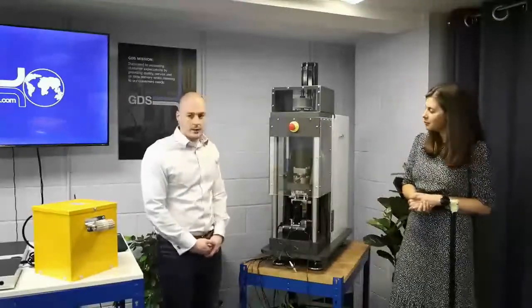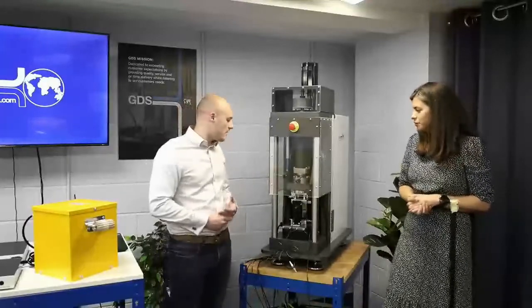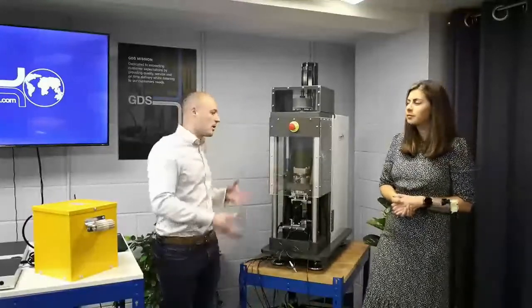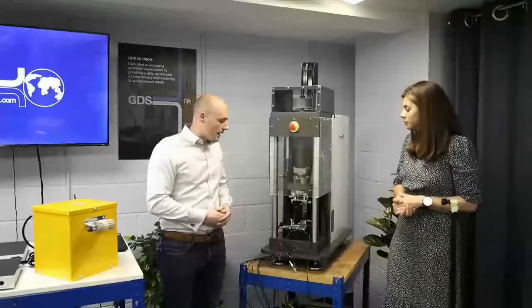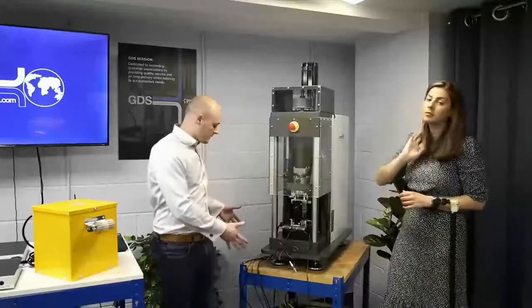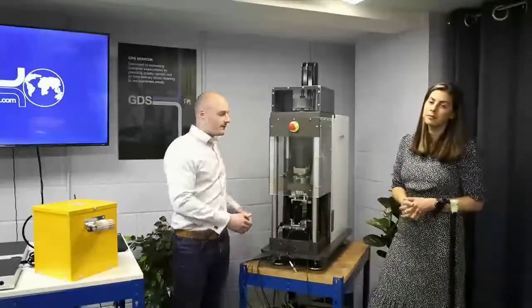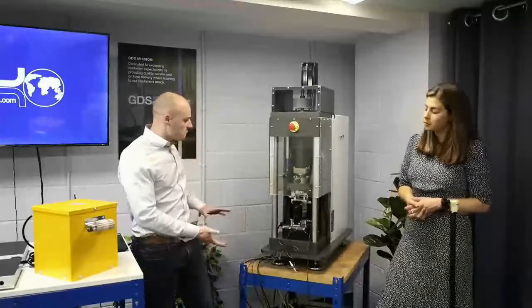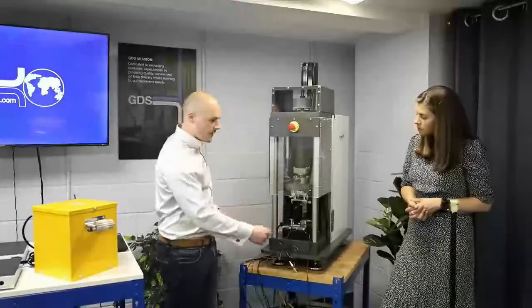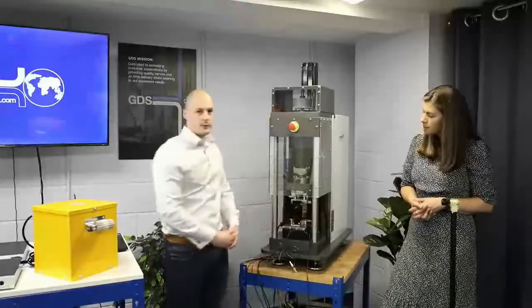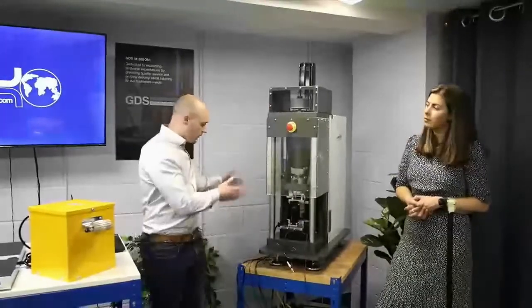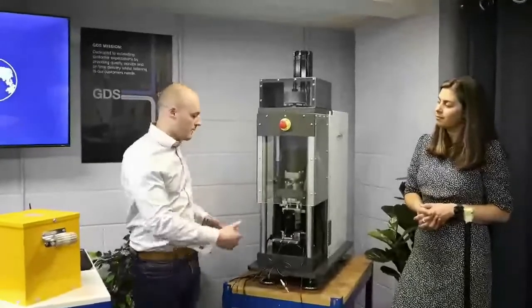These are considerations for installation. If the machine arrives, it's got to be put up onto a bench potentially. So bench capacity, load capacities, all that sort of thing need to be taken into consideration. Orientation of the machine: good orientation is frontward facing, so we get access from all 3 sides for sample installation, but it can be fitted long ways on a bench and still give good access from 2 sides.